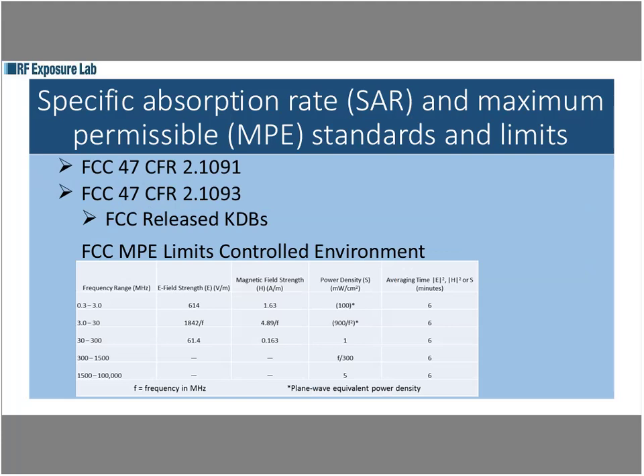And then here are the two requirements for the MPE and SAR. That's where the FCC calls out for meeting the requirements of MPE in CFR 2.1091 and 2.1093. Those two paragraphs within the CFRs are basically the law that you have to meet, either the SAR requirements or the MPE requirements, before you can release a device within the United States. And then the FCC has many KDBs released for SAR, varying depending on what your device does, how it's used, how it's operated, and so forth. All of the KDBs also cover a lot of the SAR requirements.